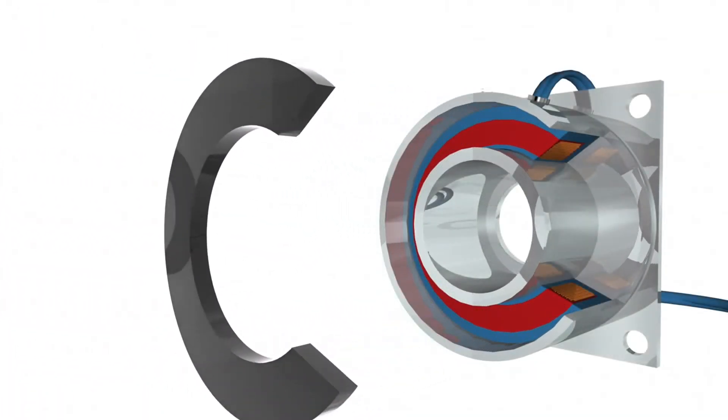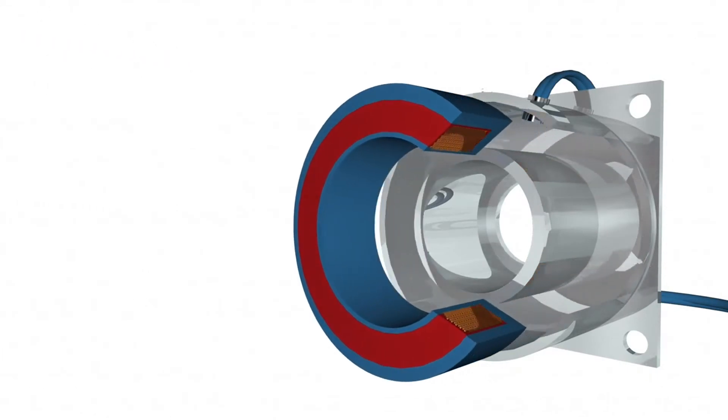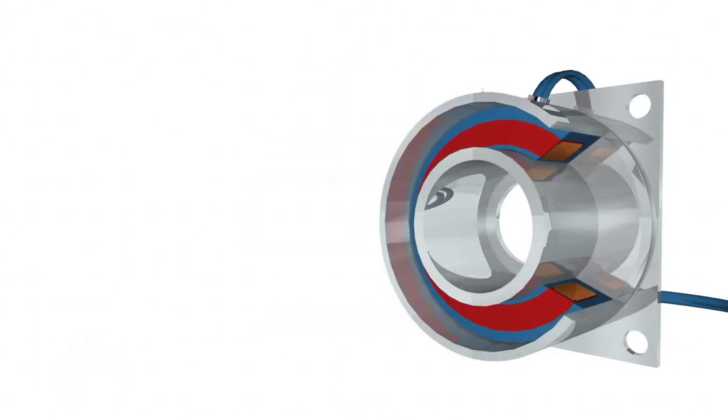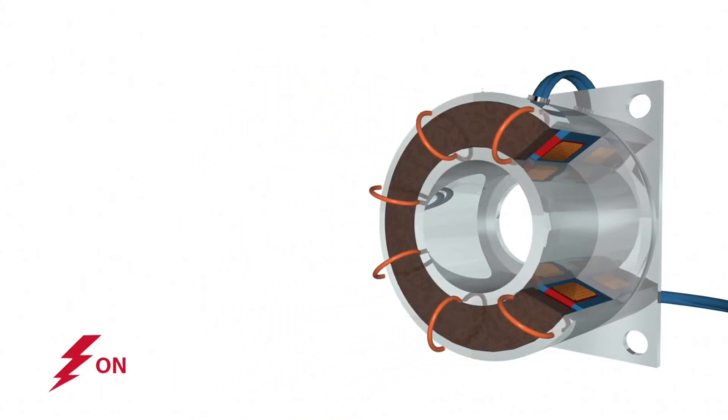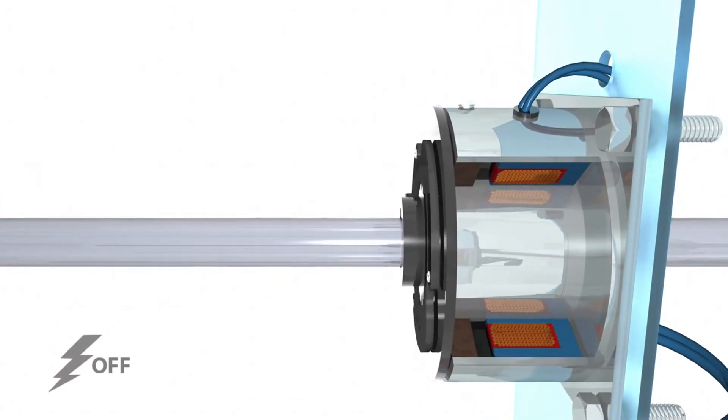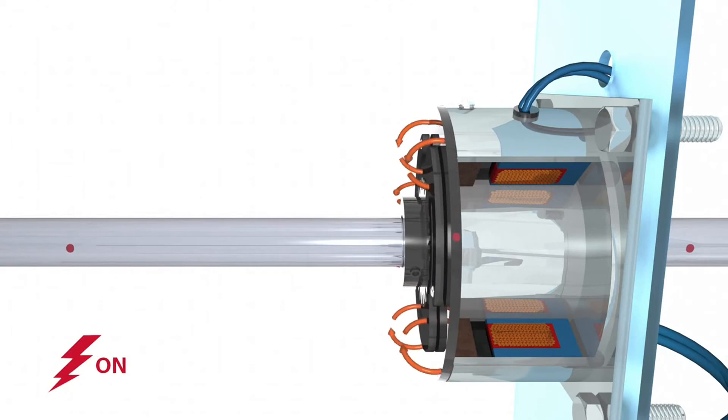Electromagnetic brakes operate via an electric actuation but produce torque mechanically. When voltage or current is applied to the brake, the coil becomes an electromagnet and produces magnetic lines of flux. This flux travels through the small air gap between the field coil and the armature, magnetically pulling the armature against the hub and creating a holding force.